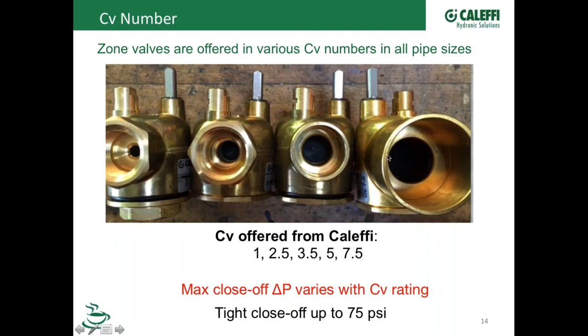Now if you look at the numbers on that, we can put 19 gallons a minute through a 1-inch copper pipe with a 4 feet per second velocity on it. But this valve at that kind of flow rate, I ran some calcs on this before we started, you're going to have about 4.83 PSI that you have to shut off against, that delta P on that valve with that kind of flow rate going through it.